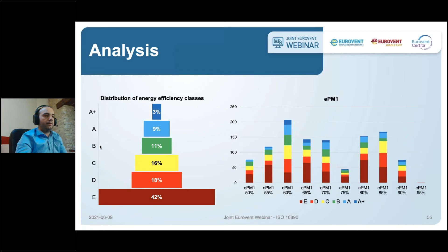The conclusion relates to what was discussed before: first you have to define your target filter efficiency. It's very important not to skip this step. You shall not define an energy or energy consumption target first. The first purpose of an air filter is to remove dust from the air, so the first step is to target filter efficiency, first the group EPM1, 2.5 and 10, as explained in the previous presentation, and then define the value of efficiency in percentage, as discussed before.